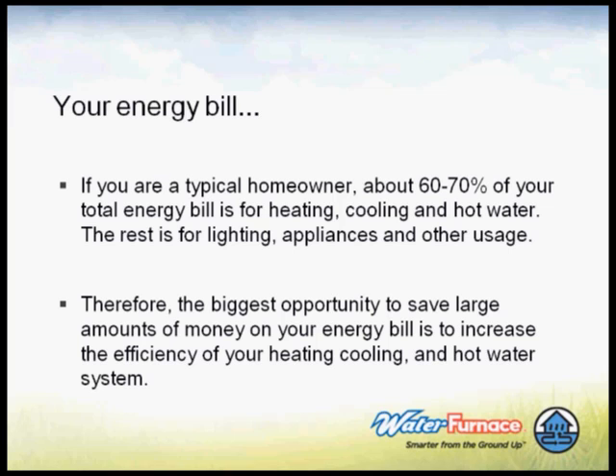Our calculations, and Larry may agree or disagree, but we found the most economical way for us to put in a system is if it can cover the heat load on the house down to about 17 degrees outside air temperature. It's not that often we get below 17 degrees, throwing out last winter, which was a 57-year winter. In a typical install, yeah, last year somebody would have had to pay for more resistance heat, but the point is they had it, they were comfortable. Hopefully next winter won't be like that. On average, you'll use about $60 to $70 in backup heat. We look for 15 to 17 degrees, what I like to call balance points.